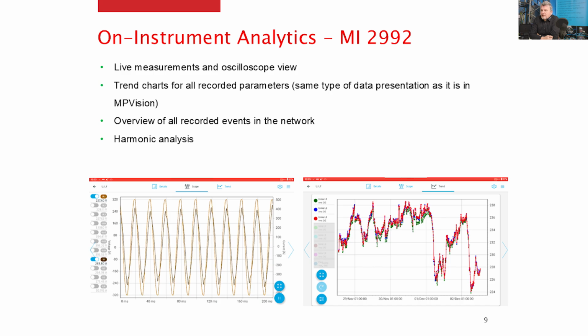Based on a color touch display, we are also enabling live measurement and oscilloscope view in the instrument. So all trend charts for all online recording parameters can be monitored on the display. There is also a new function: when you connect the voltage, and recording is not started, the trend is working, which was not the case for the previous platform. You can also monitor all recorded events in the network simply on the display. You can make a preview or pre-analysis on the instrument itself, also during recording. And the whole harmonic analysis can be checked directly on the instrument.